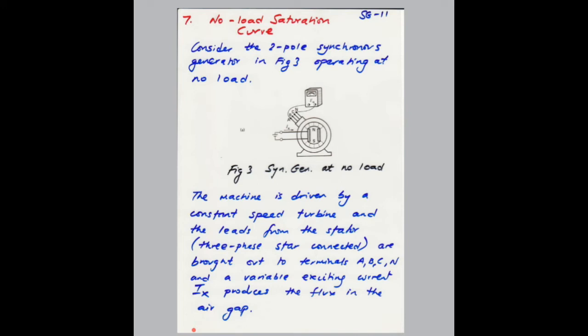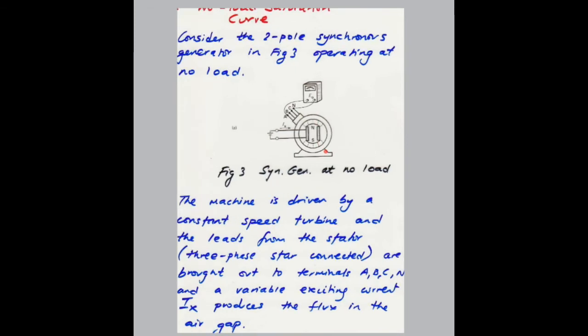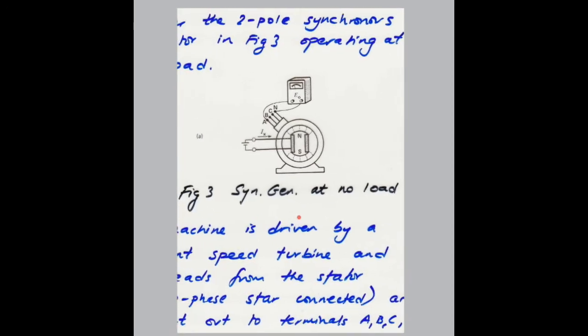So when we look at the excitation system of the machine, if you look at figure 3, we're now interested in varying the excitation current Ix and looking at how the voltage of the machine responds when we vary the excitation current. So this is a two-pole machine, cut in north and south, and the field is connected, passing through the stator winding, and the three-phase winding ABC there, and the neutral is fitted there. And we basically measure the phase voltage. So from phase A and the neutral, we're measuring this voltage.